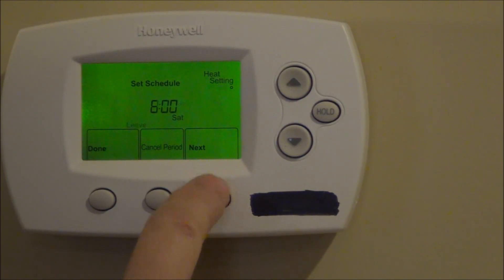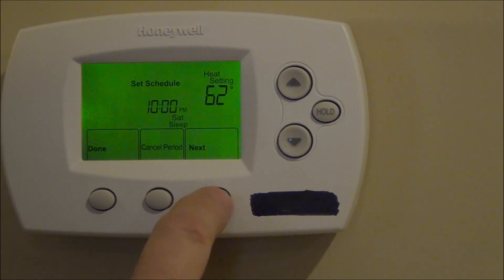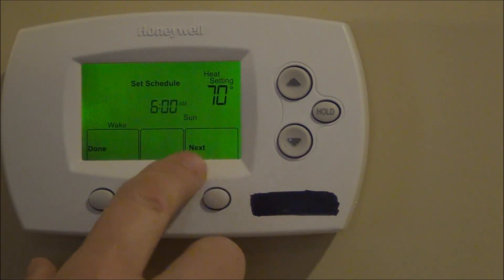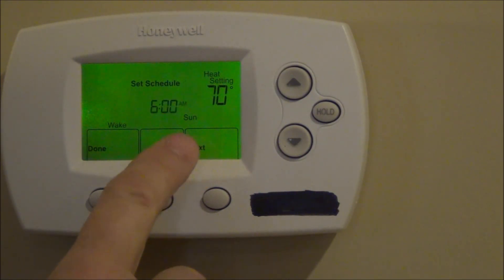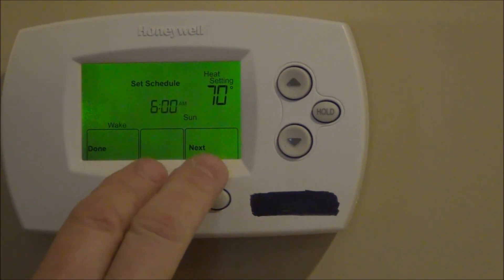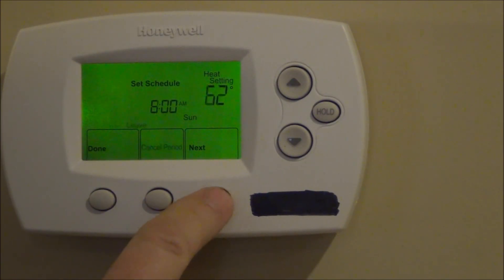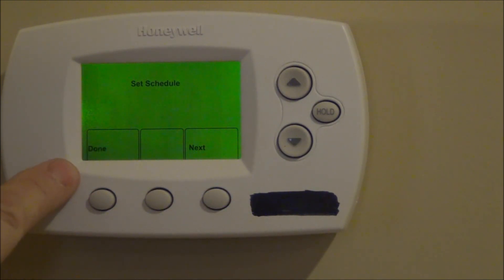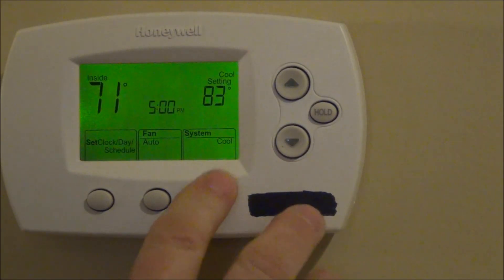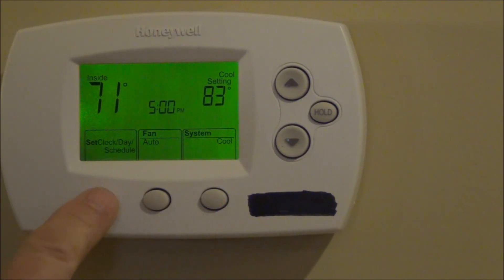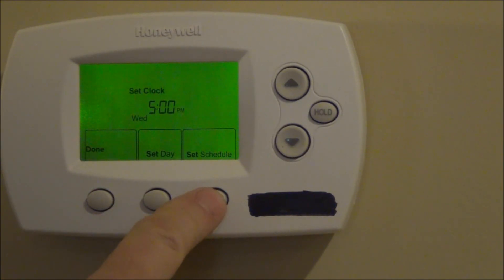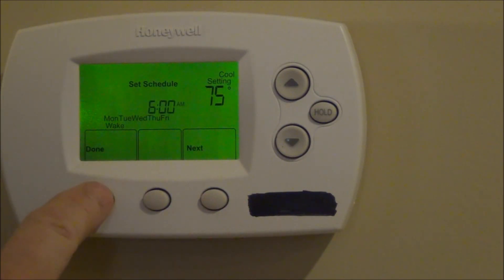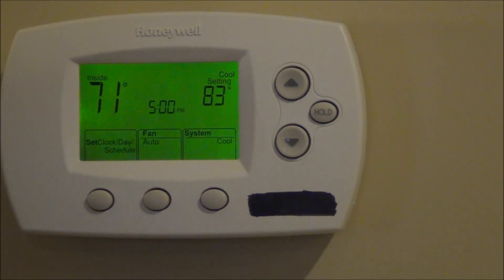As we toggle through those we can adjust the time and temperature. Press next again — on this particular model, which is a 5-1-1 model, we get Sunday. Some models have Saturday and Sunday combined; this model has them separate. We'll have the same four function times through Sunday, and when we're done, press done and your schedule is set. The final setting you want to make is your cool. Toggle to cool mode, press the set day clock schedule button, press set schedule, and go through all the same steps we did under heat mode to set the schedule for air conditioning. Press done when finished and now the thermostat is set.